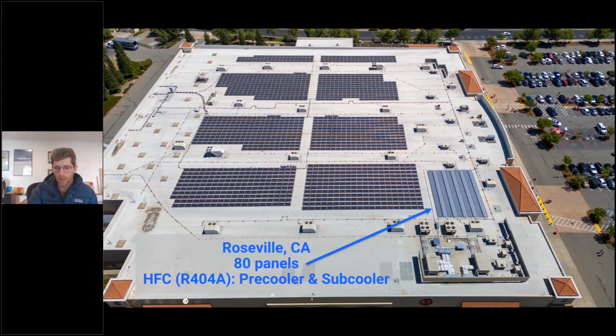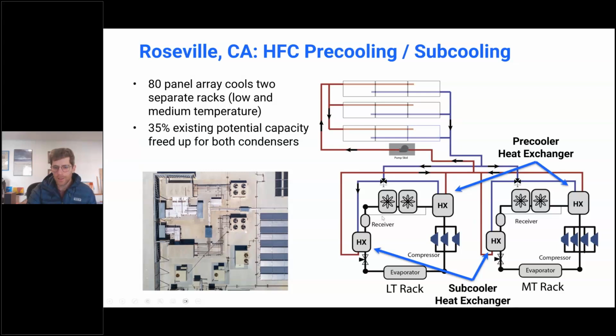But in this case, we are doing this pre-cooling and subcooling for 2 refrigeration systems. We installed 80 panels at this site, and before we installed these panels, the existing condensers were more or less at the end of their life. But this particular store is slated for a remodel in 2027. And so the building owner didn't want to replace the condensers this past summer because those condensers would become a stranded asset, because the next refrigeration system is going to be a CO2 one, and all of this equipment will be removed. And so what we were presenting to them is essentially using the panels to add heat rejection capacity to the condenser cycle in the summer.